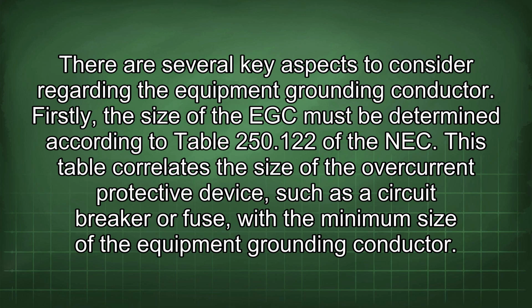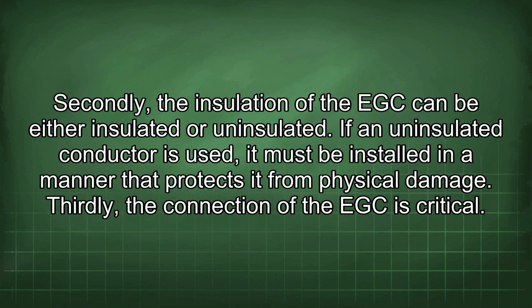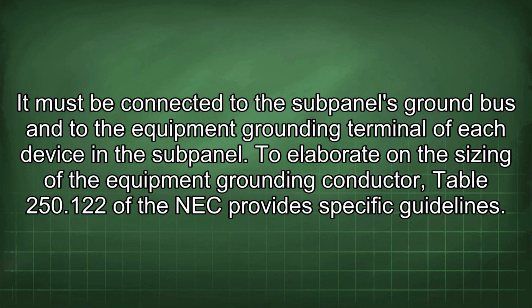Firstly, the size of the EGC must be determined according to Table 250.122 of the NEC. This table correlates the size of the overcurrent protective device, such as a circuit breaker or fuse, with the minimum size of the equipment grounding conductor. Secondly, the insulation of the EGC can be either insulated or uninsulated. If an uninsulated conductor is used, it must be installed in a manner that protects it from physical damage. Thirdly, the connection of the EGC is critical. It must be connected to the subpanel's ground bus and to the equipment grounding terminal of each device in the subpanel.